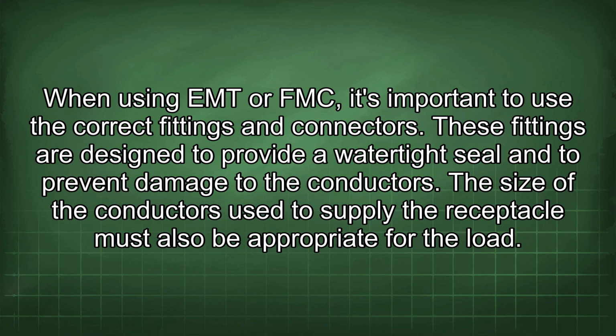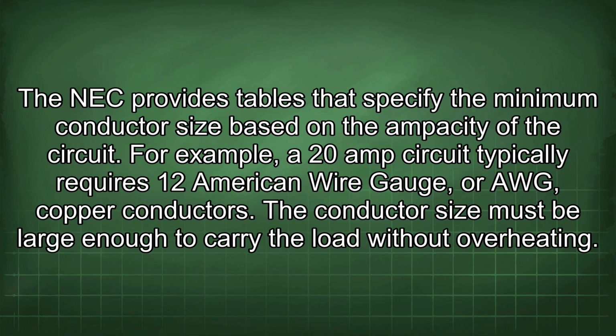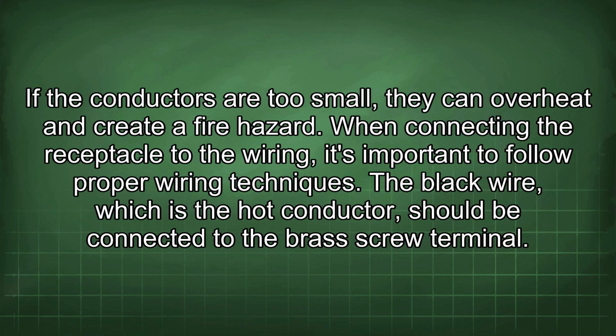The size of the conductors used to supply the receptacle must also be appropriate for the load. The NEC provides tables that specify the minimum conductor size based on the ampacity of the circuit. For example, a 20 amp circuit typically requires 12 American wire gauge, or AWG, copper conductors. The conductor size must be large enough to carry the load without overheating. If the conductors are too small, they can overheat and create a fire hazard. When connecting the receptacle to the wiring, it's important to follow proper wiring techniques.